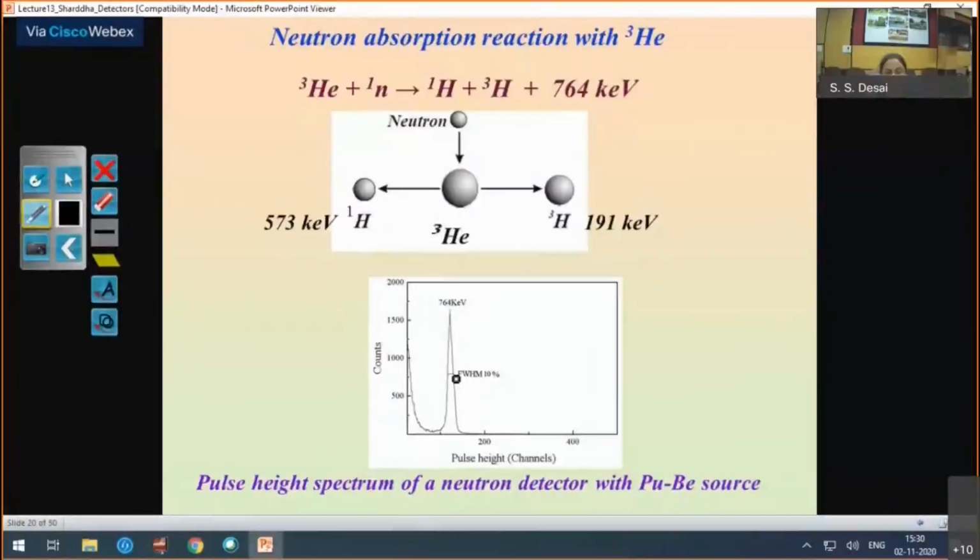It shows that all the pulses created by one helium-3 neutron interaction give nearly the same amplitude, that is, the same amplification factor M. This is where the complete symmetry of the detector, including hardware symmetry as well as gas purity, is reflected in a very good pulse height distribution.